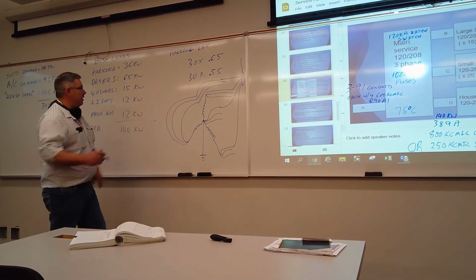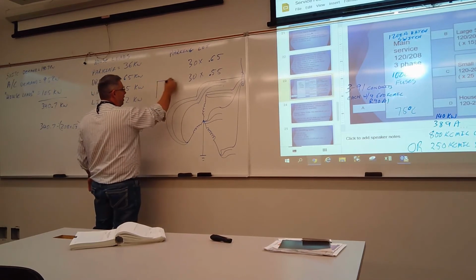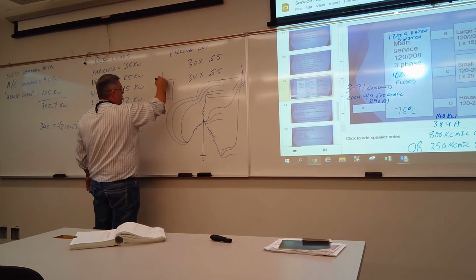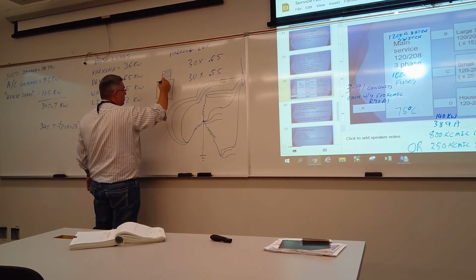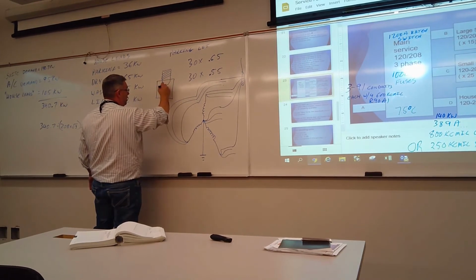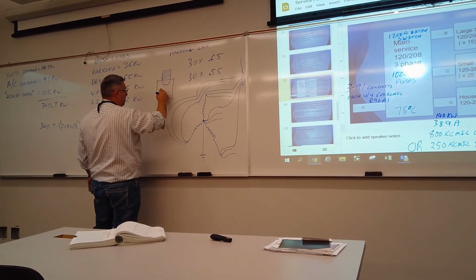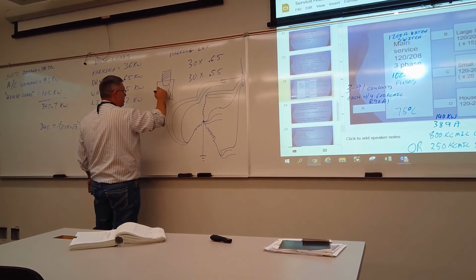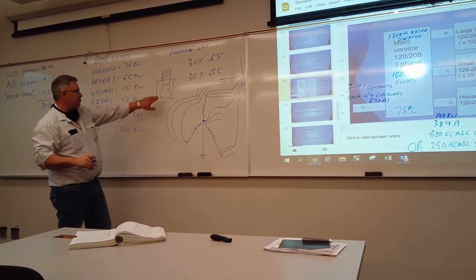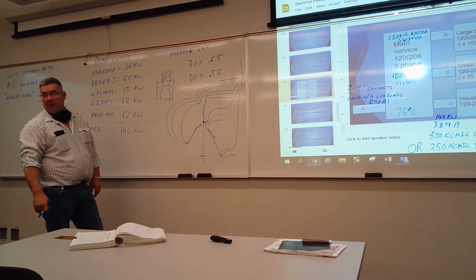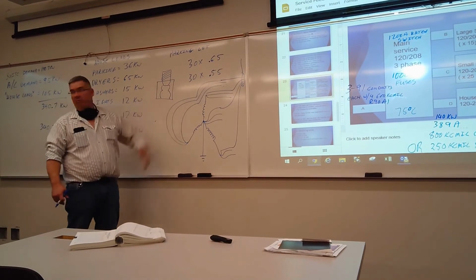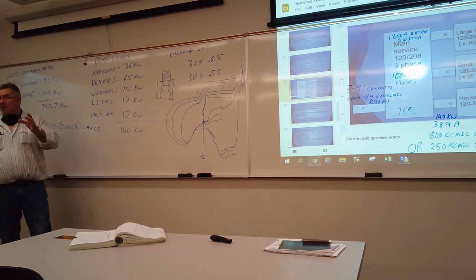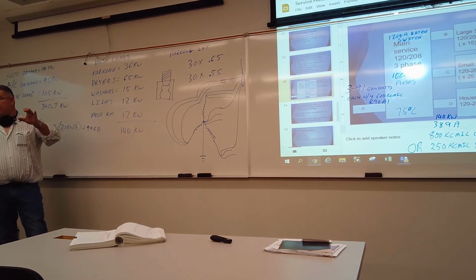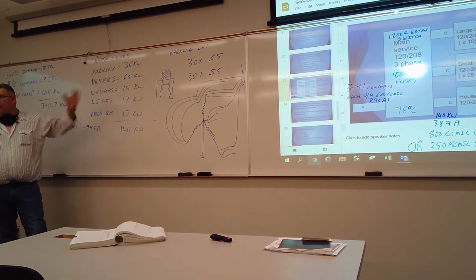And generally, a lug that's rated for multiple conductors, when you look at it from the end, there's a screw, or a set screw, that comes in the top. Usually it has an Allen wrench, and then it screws down. It's wider at the bottom and then a smaller one on top, so you put your two conductors in and tighten your lug down. Or you could use side by sides. They make a block that has provisions for 6 conductors on them. Sometimes there's 3 doubles. There are all kinds of different configurations. But you just make sure that you've got some way of connecting them.